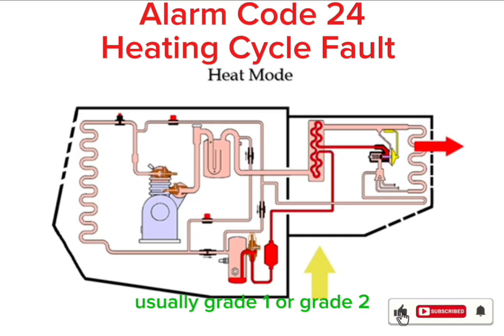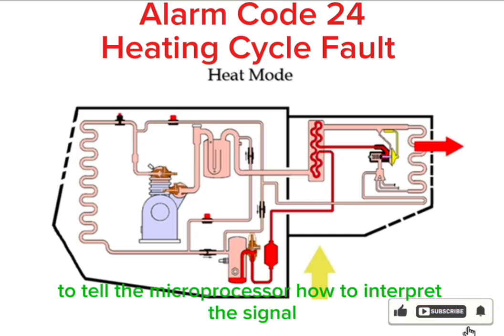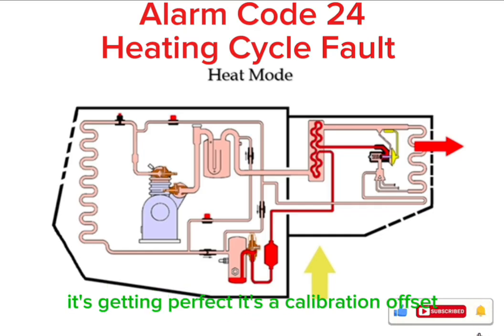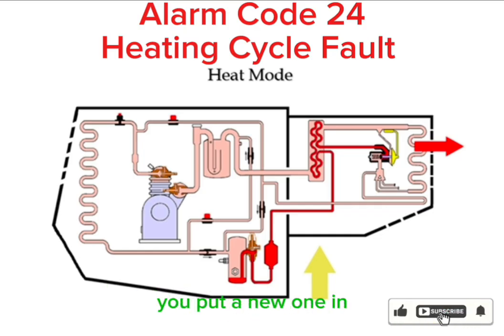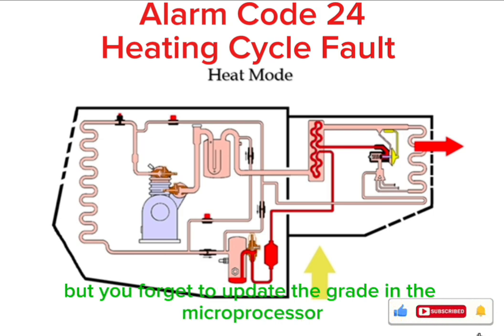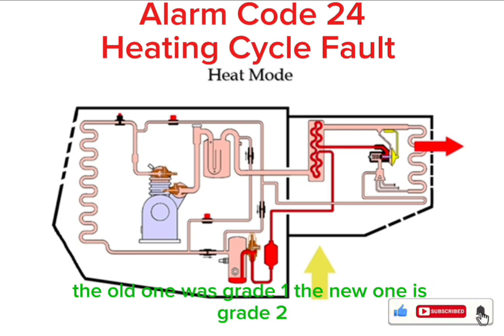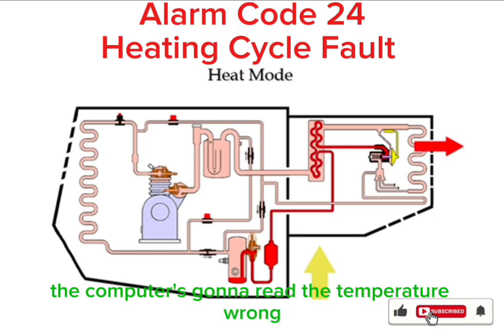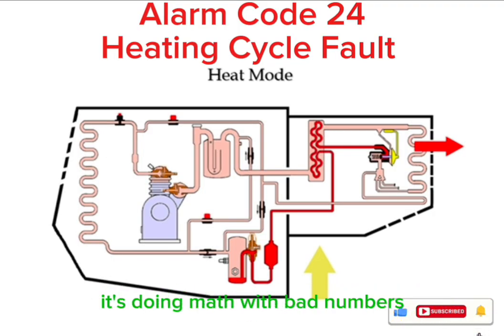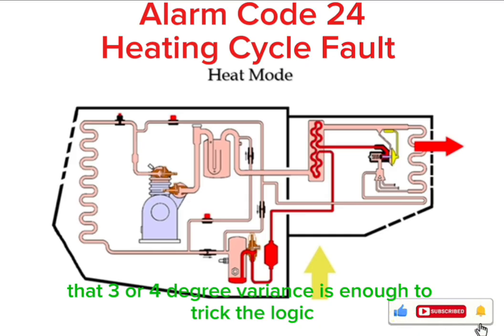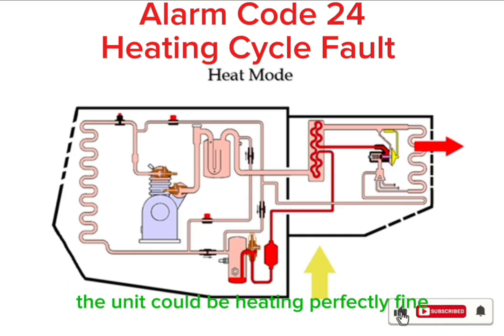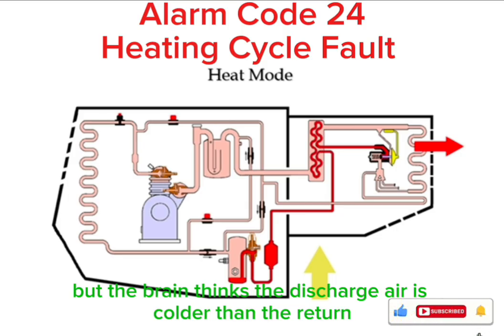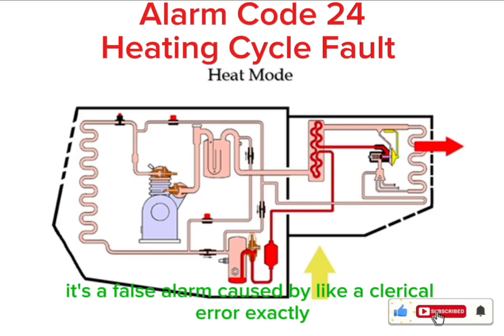So we grade them, usually grade 1 or grade 2, to tell the microprocessor how to interpret the signal it's getting. Perfect. It's a calibration offset. So now imagine you replace a sensor, you put a new one in, but you forget to update the grade in the microprocessor. The old one was grade 1, the new one is grade 2. The computer's going to read the temperature wrong. It's doing math with bad numbers. That 3 or 4 degree variance is enough to trick the logic. The unit could be heating perfectly fine, but the brain thinks the discharge air is colder than the return because of that bad calibration. It's a false alarm caused by a clerical error?